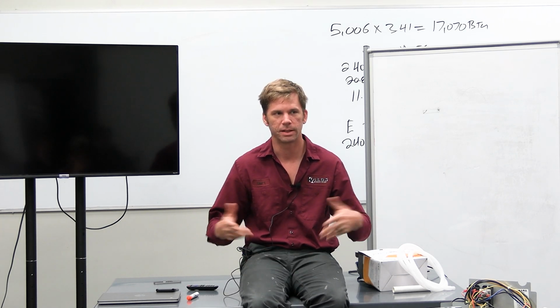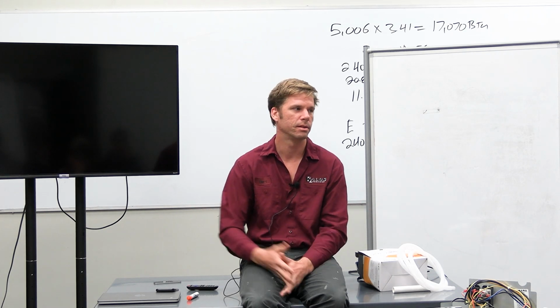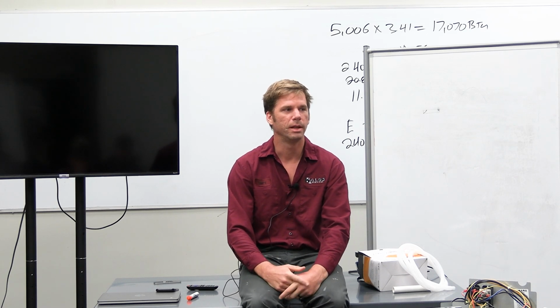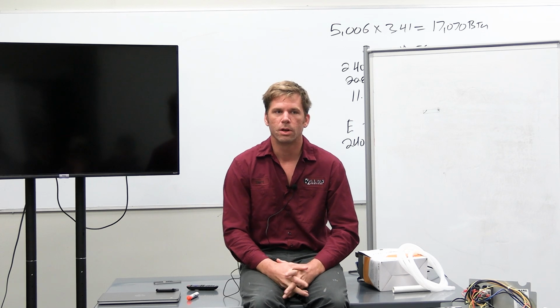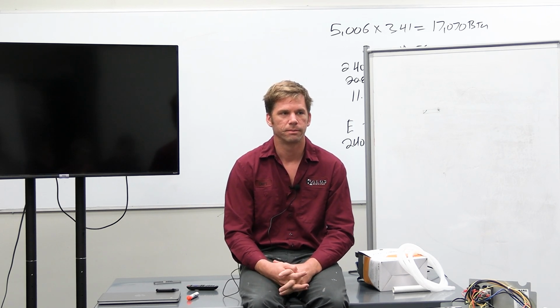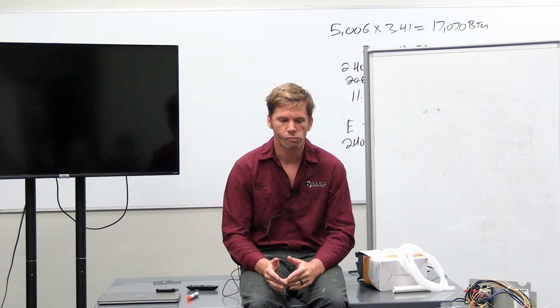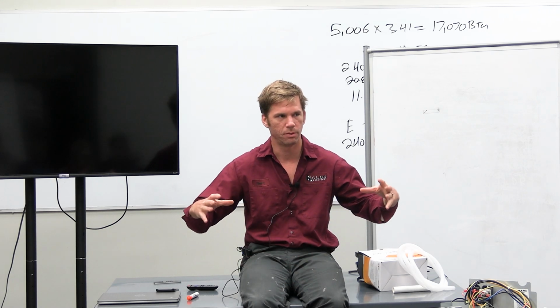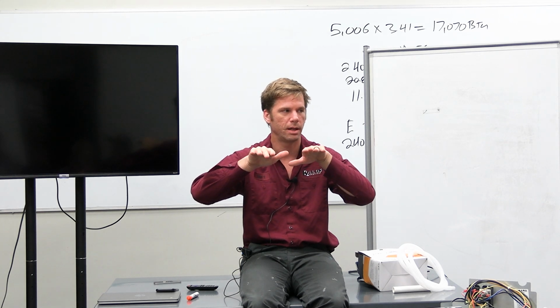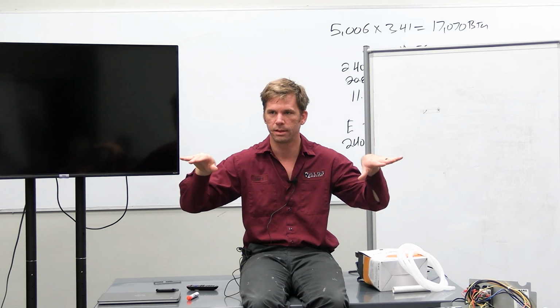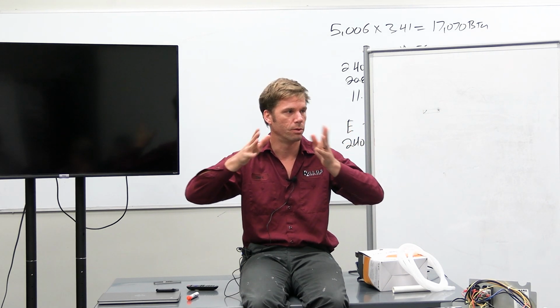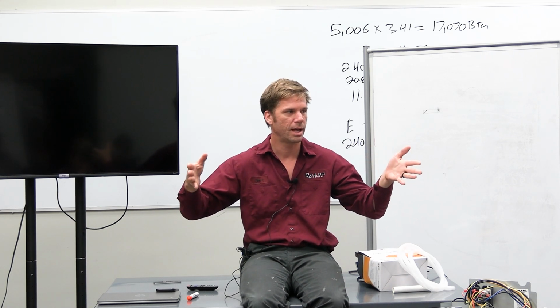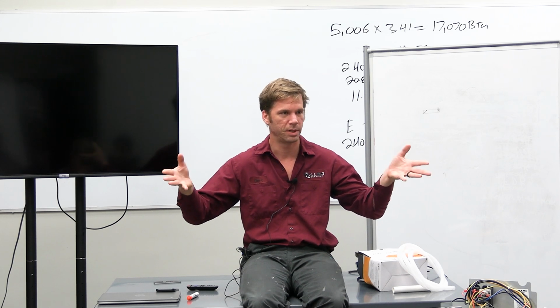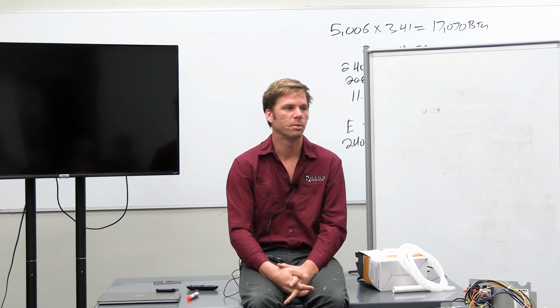On that note, when you have heaters that are really rusted out, and that's pretty common because you have a heater that sits outside in Florida and it gets hot when it runs. It's also right there around chlorine. Maybe it's been leaking throughout the years inside the heat exchanger. We don't want to try to fix something that's going to be unsafe. And so you're going to go to a lot of heaters where the whole bottom portion is just going to be rust, and you're going to look under there and try to locate the actual burners where the gas flows through and the flame actually comes up. If those are rusted, or the supports for them are rusted, anything like that, then we just need to quote a replacement heater here. Let the customer know this is not safe to repair.